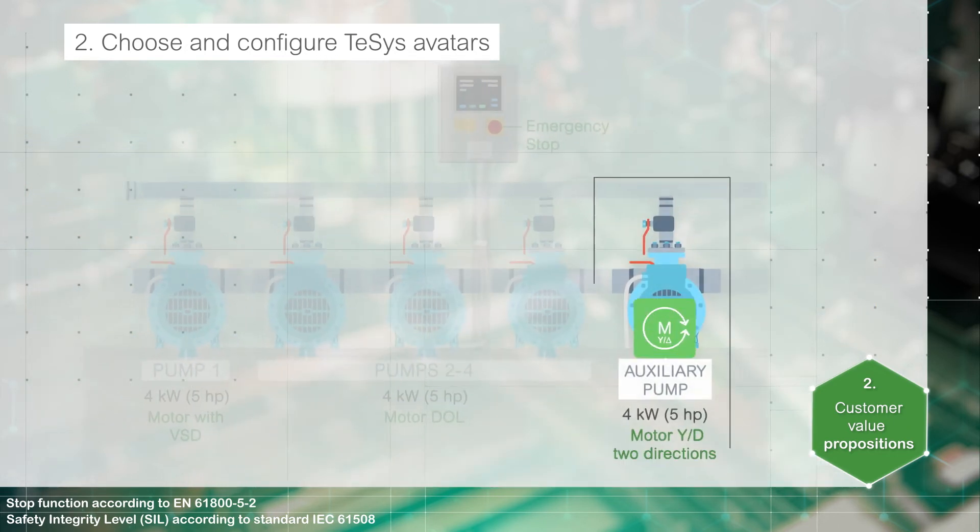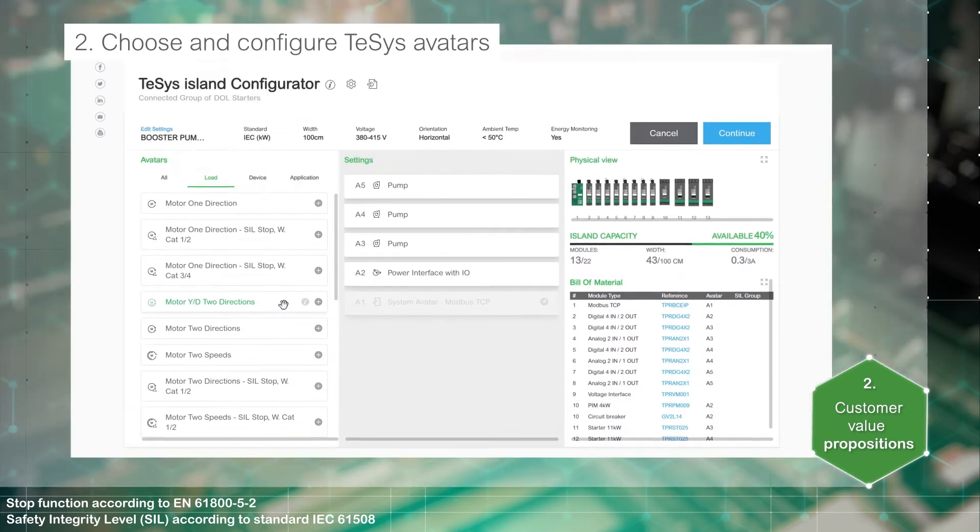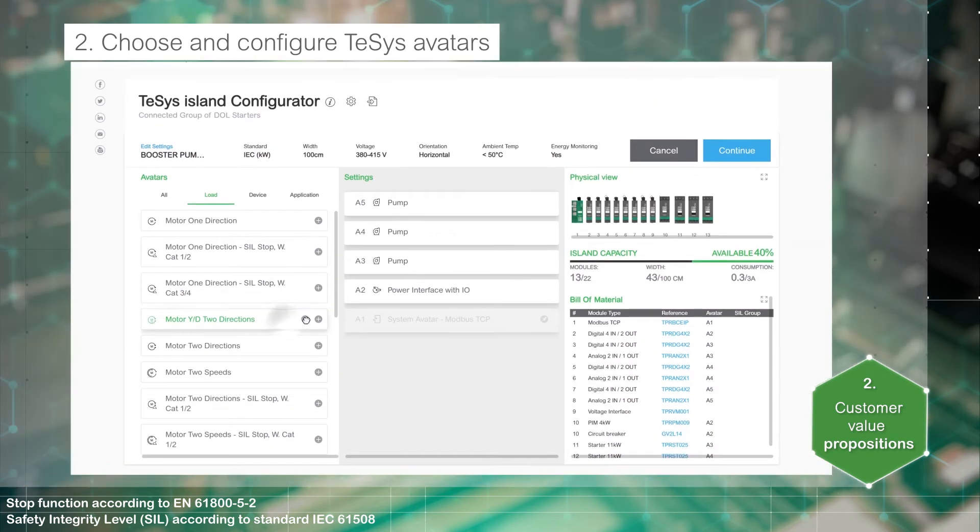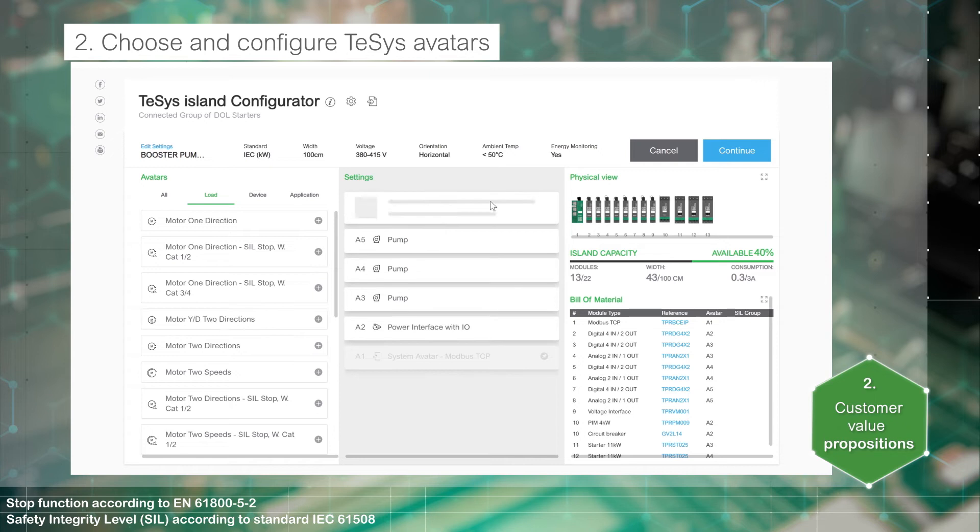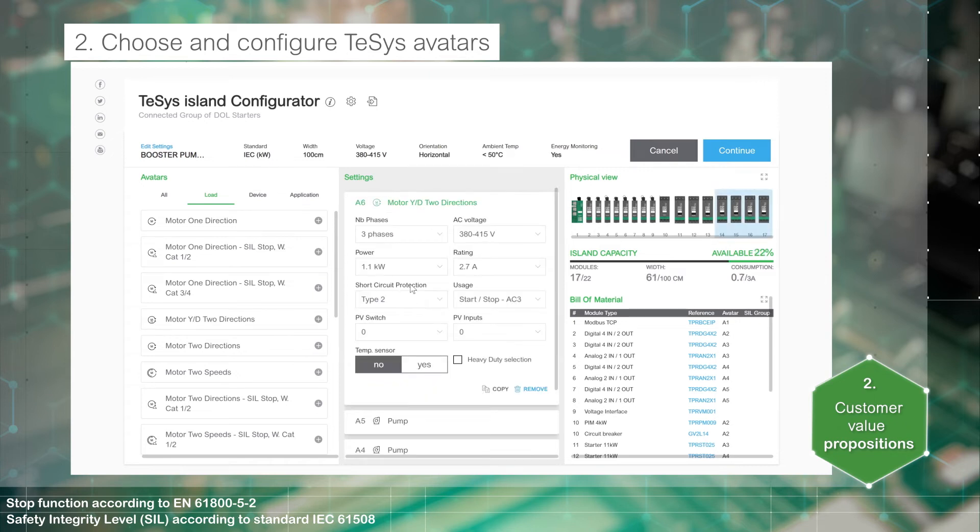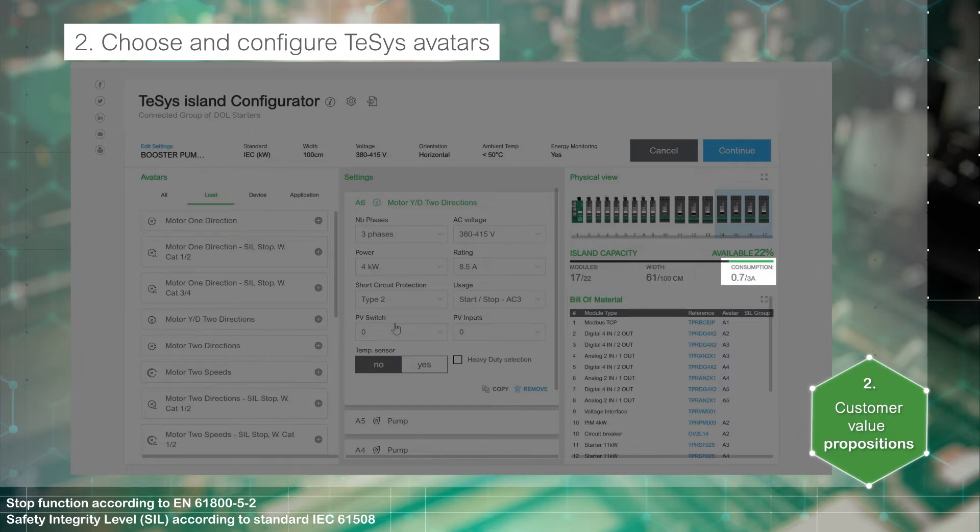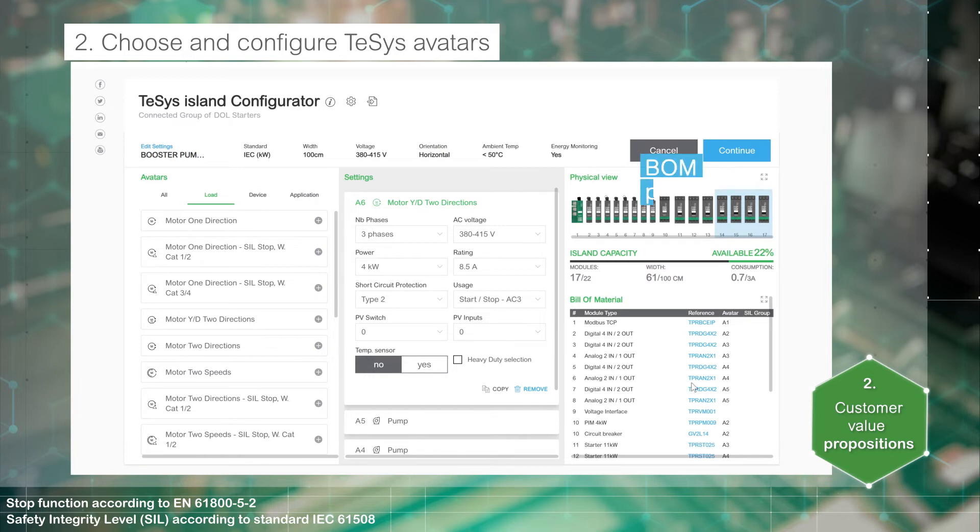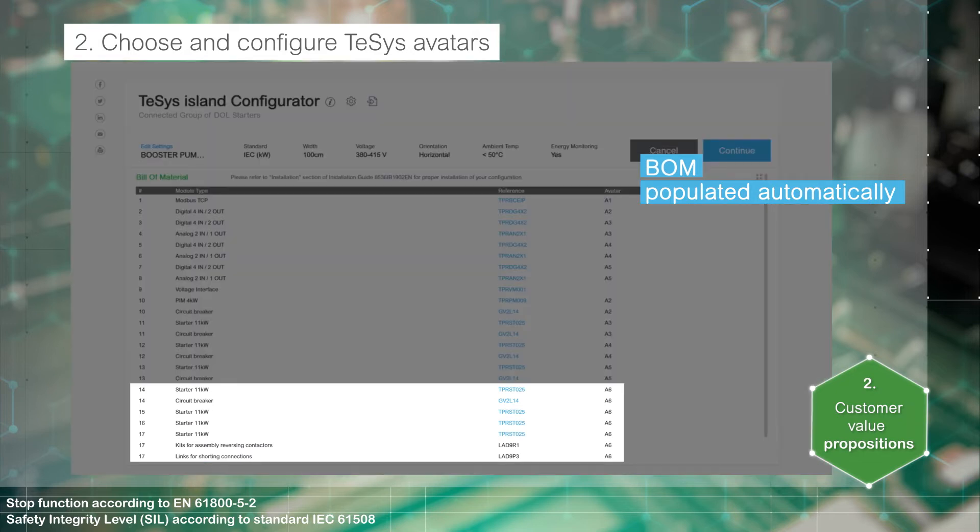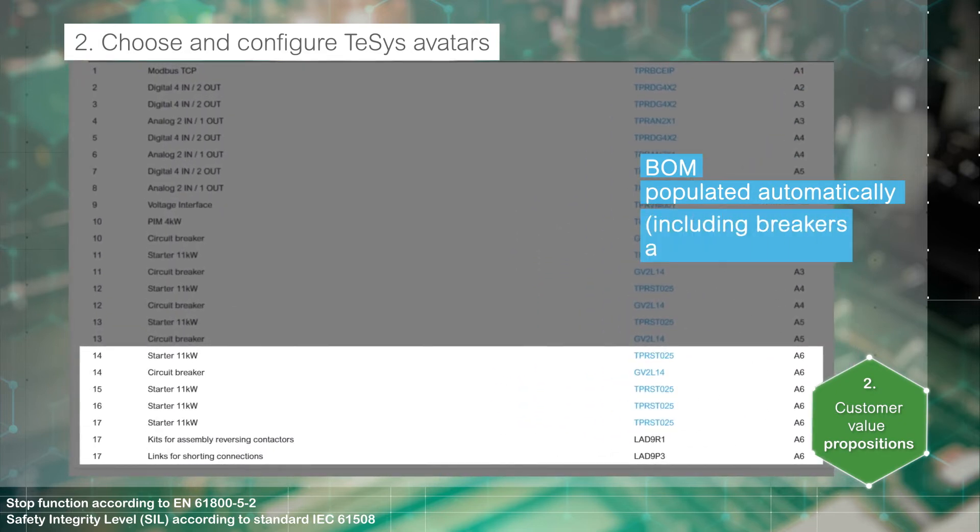Focus now on this motor. The configurator checks that the number of modules, the width of the island, and the control power consumption are compliant with the TeSys Island specifications. The bill of materials is automatically populated with the appropriate devices. It includes accessories and circuit breakers.